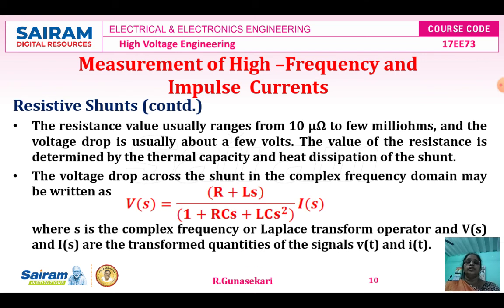The resistance value usually varies in the range from 10 micro ohms to a few milli ohms. The voltage drop is usually about a few volts only. The value of resistance R is determined by the thermal capacity and heat dissipation of the resistive shunt. The voltage drop across the resistive shunt in the complex frequency domain is: V(s) = [(R + Ls) / (1 + RCs + LCs²)] × I(s).